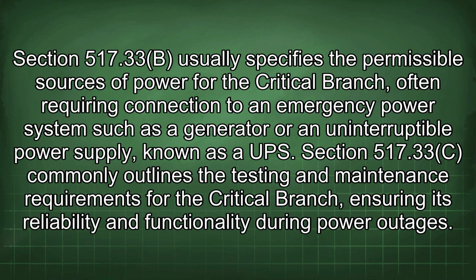Section 517.33b usually specifies the permissible sources of power for the critical branch, often requiring connection to an emergency power system such as a generator or an uninterruptible power supply, known as a UPS. Section 517.33c commonly outlines the testing and maintenance requirements for the critical branch, ensuring its reliability and functionality during power outages.